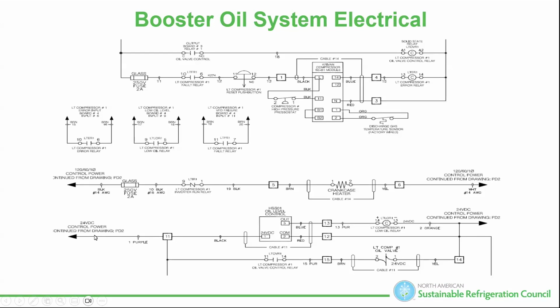24 volts DC. Oh, check this out. 24 volts DC. This is the same page. 24 volts DC, 120 single phase, 208 control. Pay attention with your meter. If you don't know how to read wiring diagrams, take the selector switch and put it on auto detect so you don't blow your meter up. And it will automatically switch AC to DC for you. But don't be that dude. Be the dude that knows.